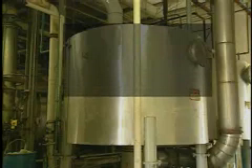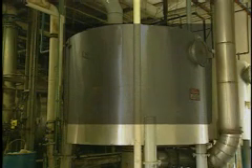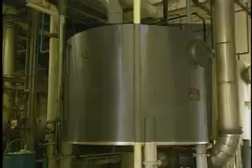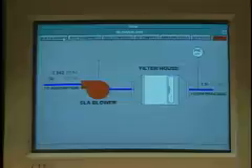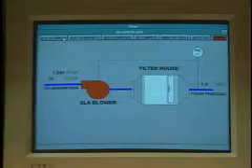Retention is affected by the molecular weight of the contaminant molecules. As the molecular weight of the molecules increases, retention increases. Moisture in the gas stream can also affect retention. Water will adsorb onto activated carbon, competing with the organic contaminant for adsorption sites. Since adsorption is also affected by the presence of liquid and solid particles in the gas stream, particulate matter must be removed before entering the adsorber.